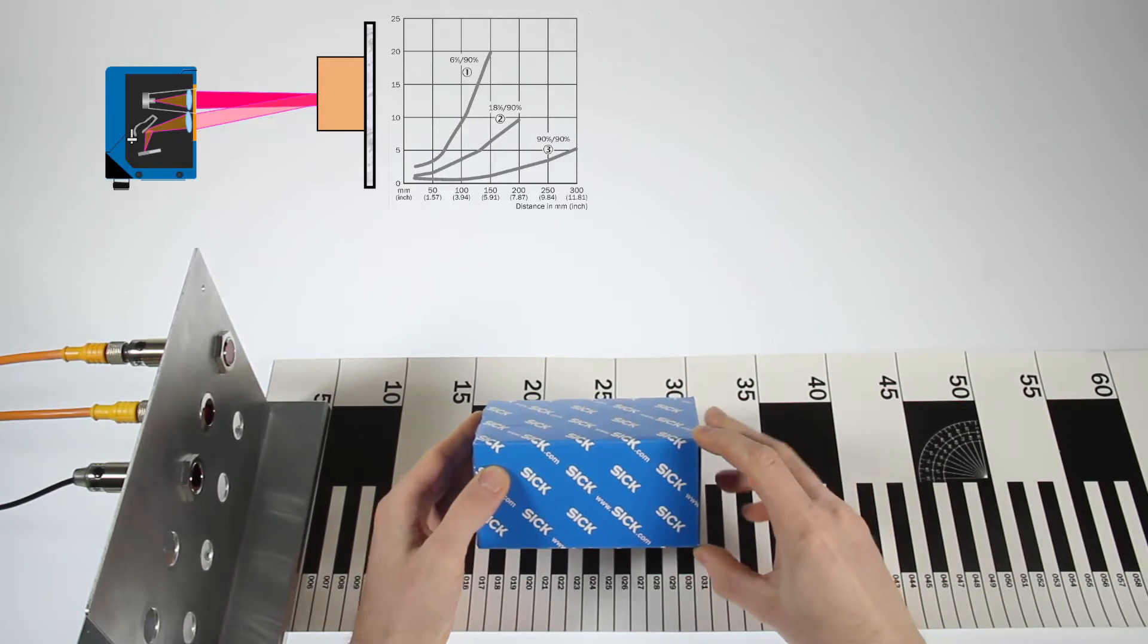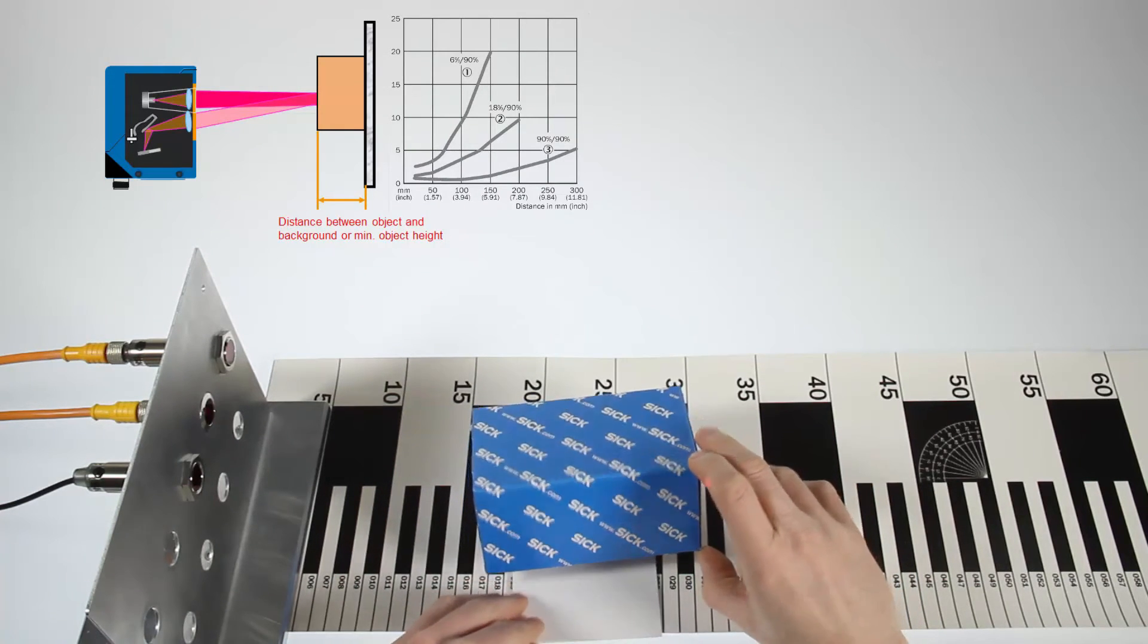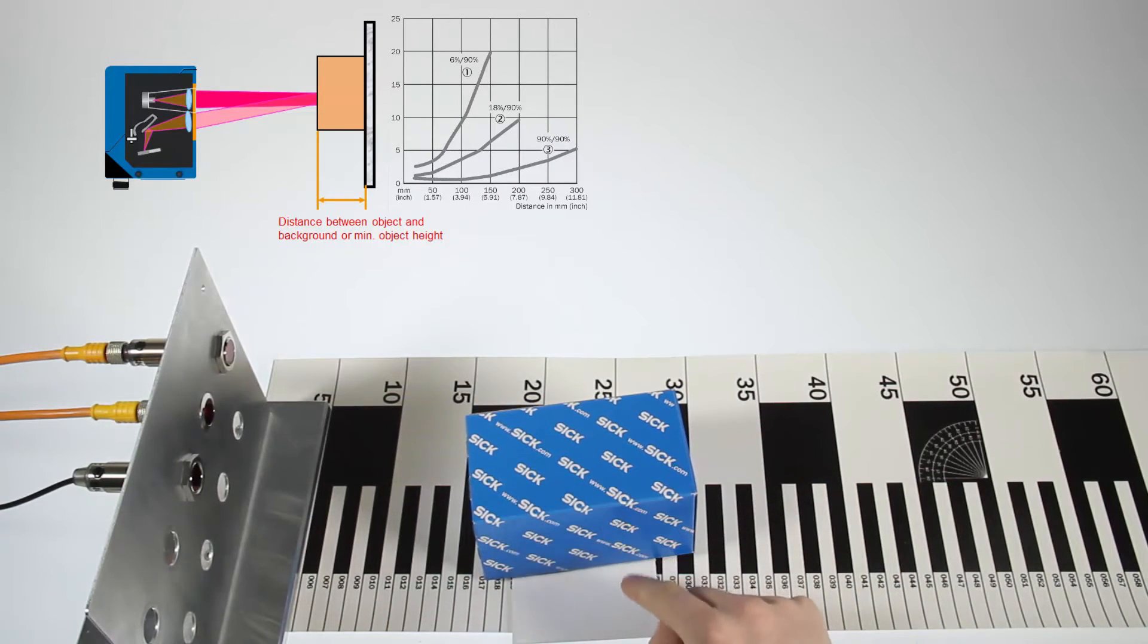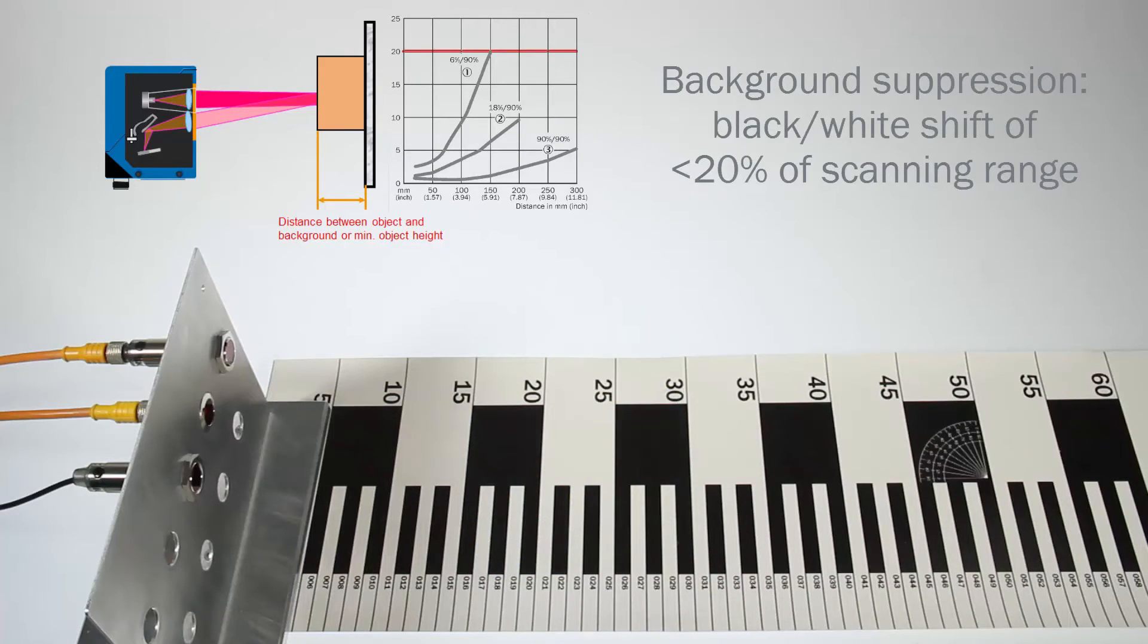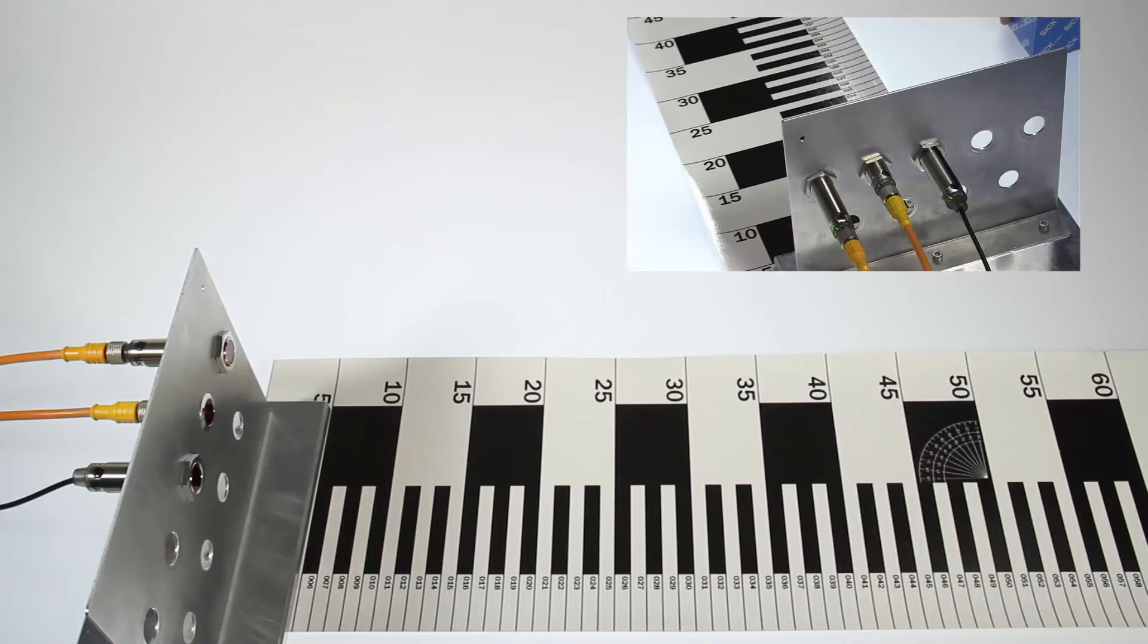just the same as the minimum object height or the necessary difference between object and background. To make use of the maximum performance of our background suppression versions, we recommend a black-white shift which is less than 20% of the set scanning range.